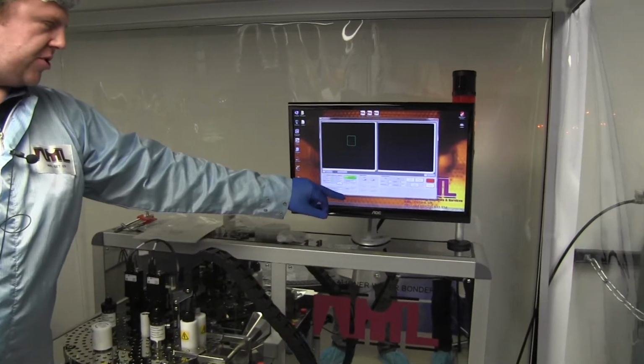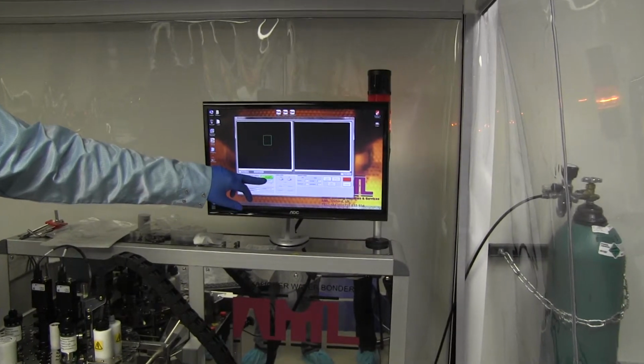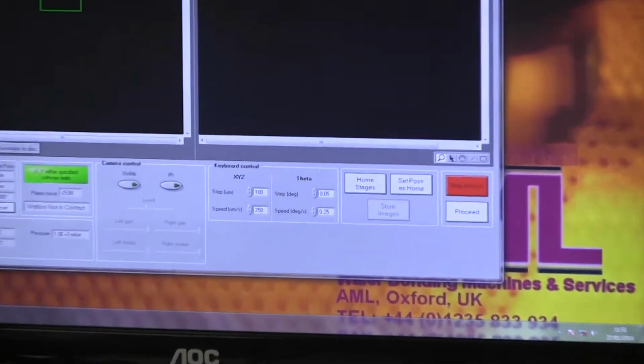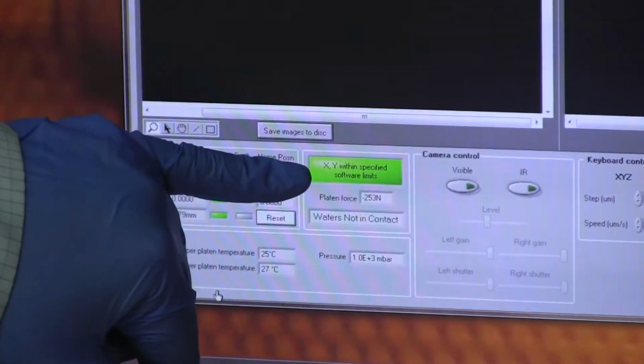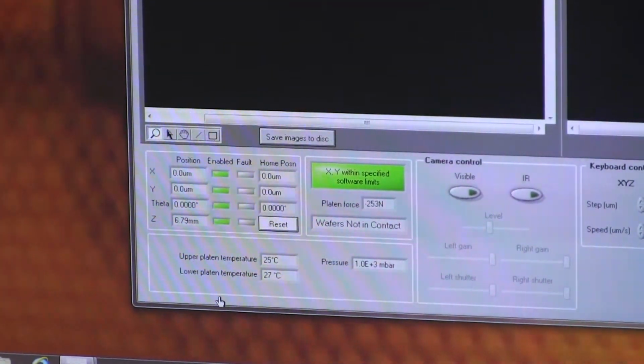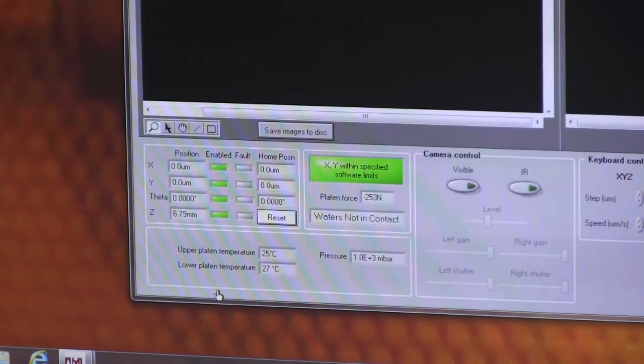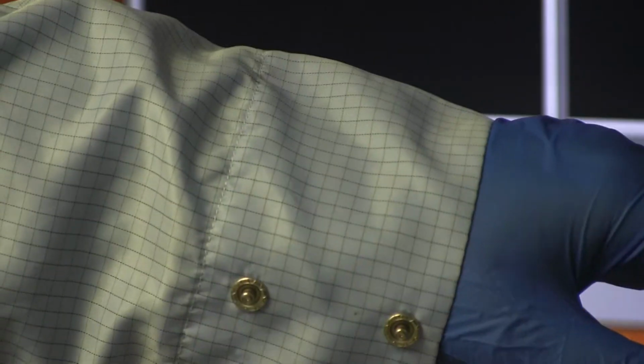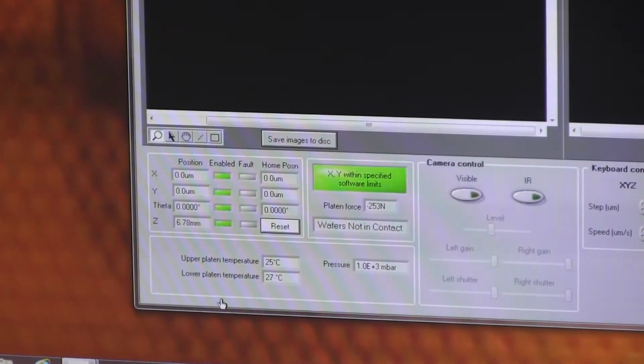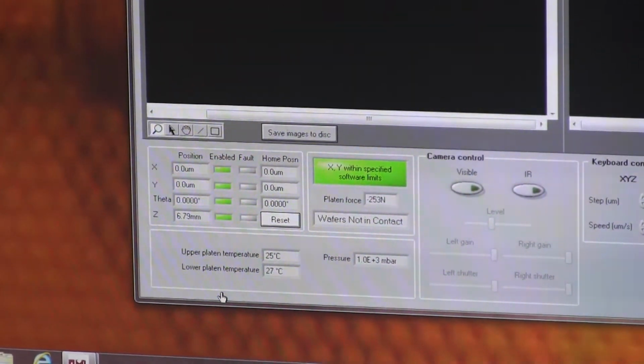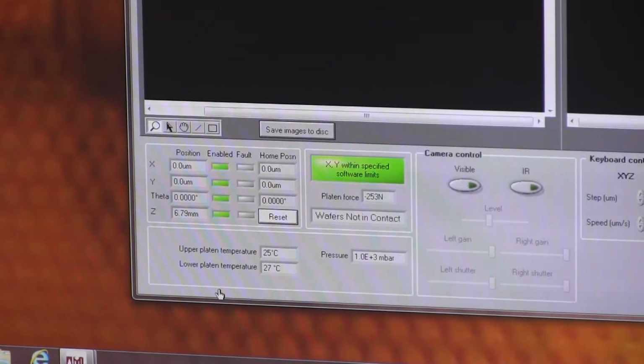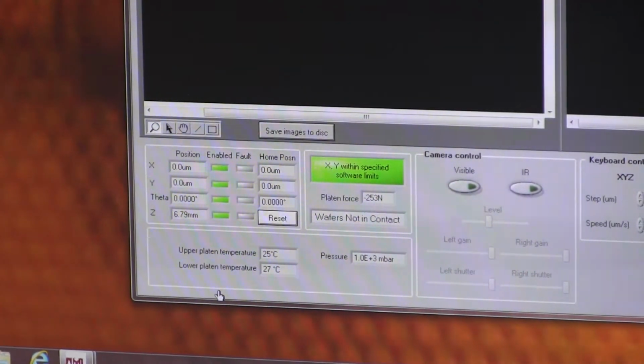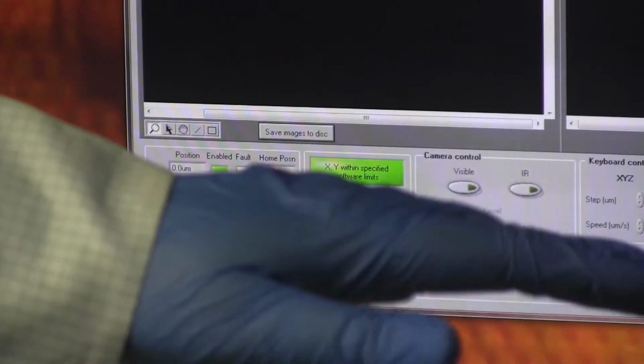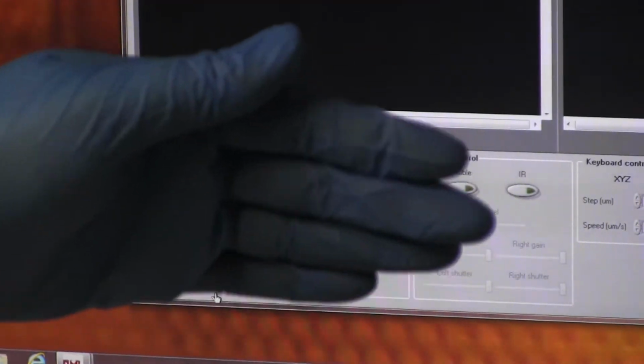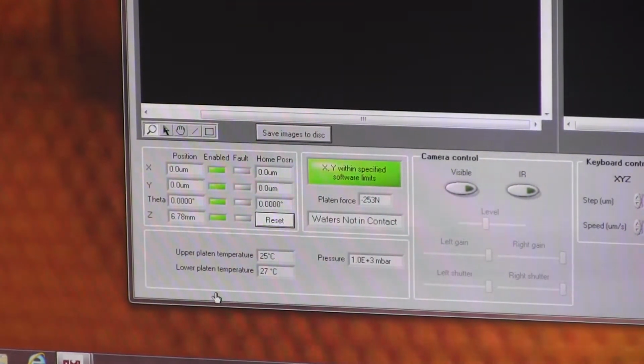We can see the platen temperatures and the chamber pressure, and here we can see any force being applied. At the moment the X and Y motors are within the specified software limits. If you run it, the software limits allow you to move 7.5 millimeters in either direction, so 15 millimeters of total travel, 7.5 either side of the center point. At the moment we're within those limits. If you reach the edge, the software will cut in and stop the motors running, and the idea is that it stops before any physical limit is reached.